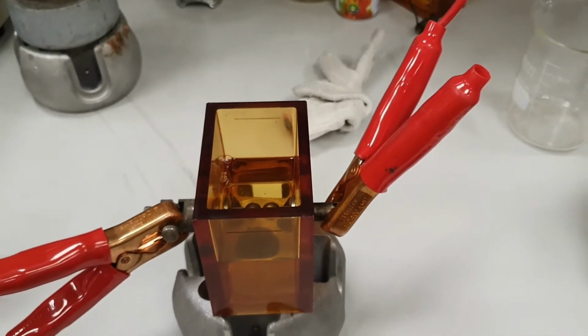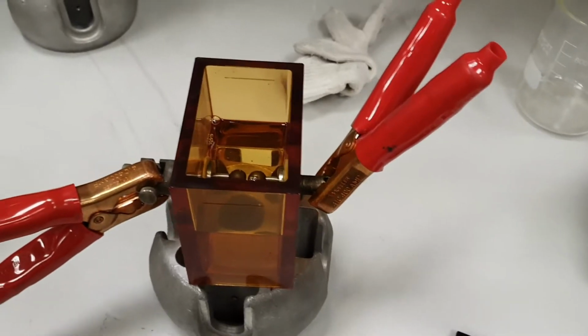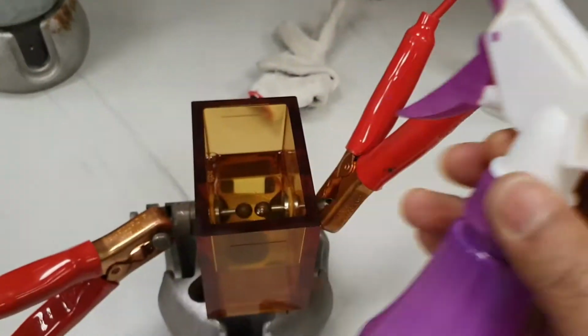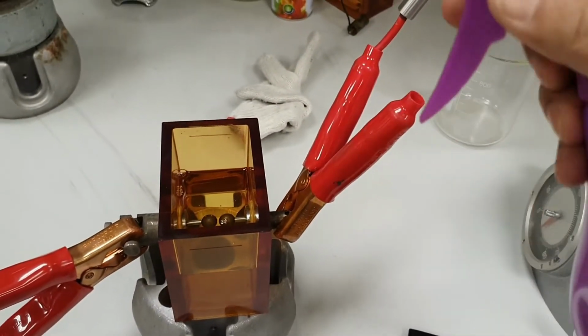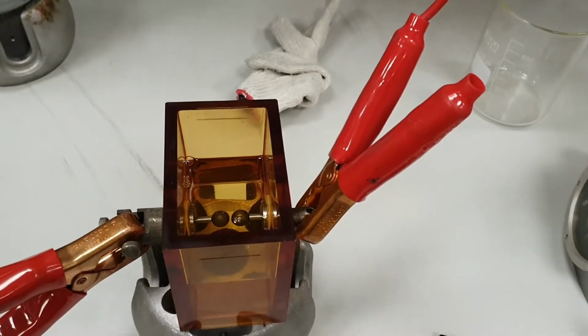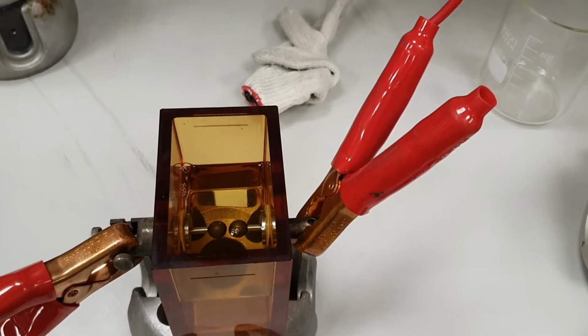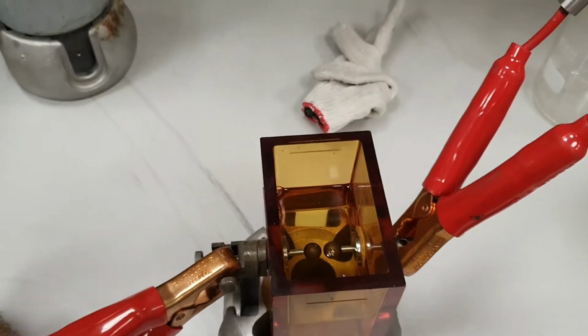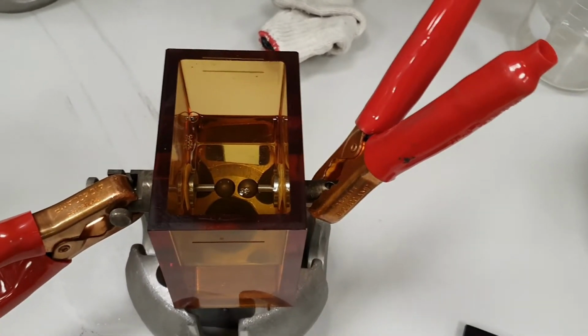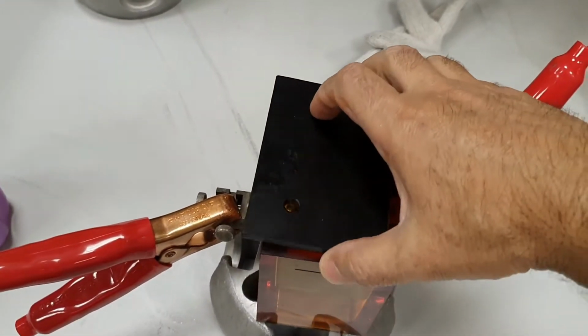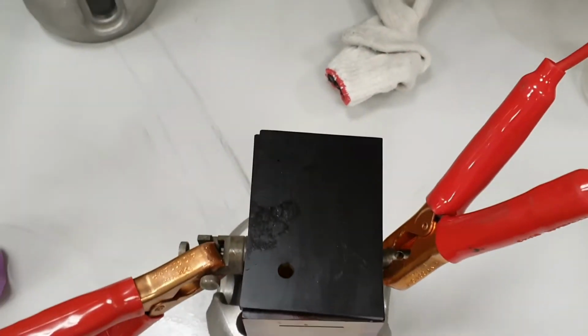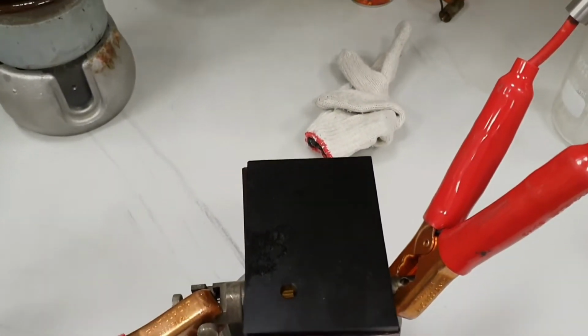Now again we need to take the measurement for a defective type of insulation in this oil. So we'll add some impurities. Impurities again we'll be using as this water, some droplets of water, so they will create moisture inside. So after you repeat the tan delta measurement for oil with some moisture in it, you will see a lot of difference in the values there.